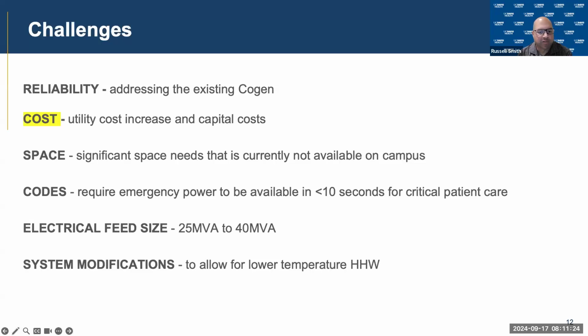Space is another thing. As the previous map showed, not much room on campus. So basically we have to remove buildings or demolish buildings in order to build the infrastructure needed for the electrification codes. Being a hospital, anything that is powered by electricity that is going to be critical to patient care has to be on emergency power. And so the addition of more emergency diesel generators is needed so that we can maintain our accreditation. We also have backup heating that's needed. We can't depend on just a single source of energy for heating. We have to have a second energy source for heating.